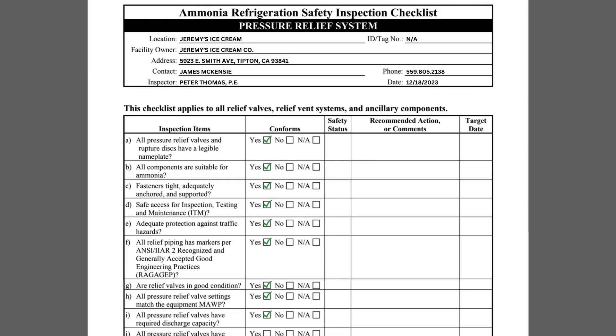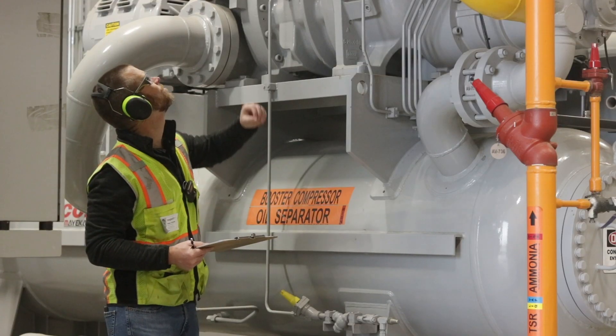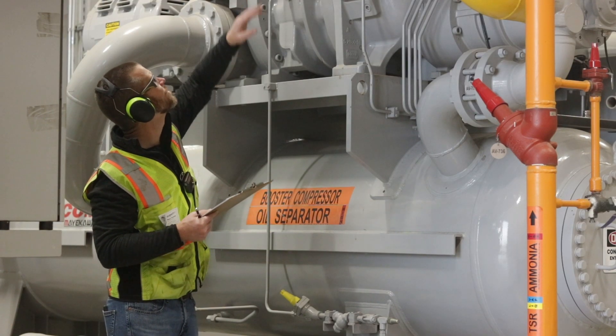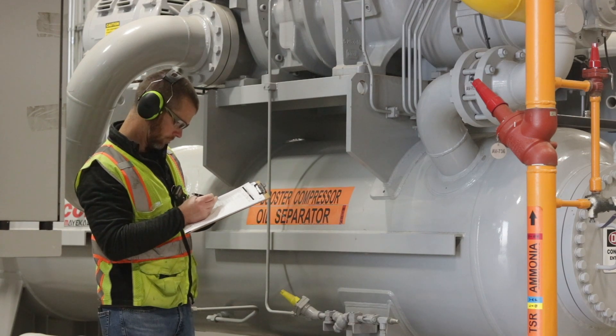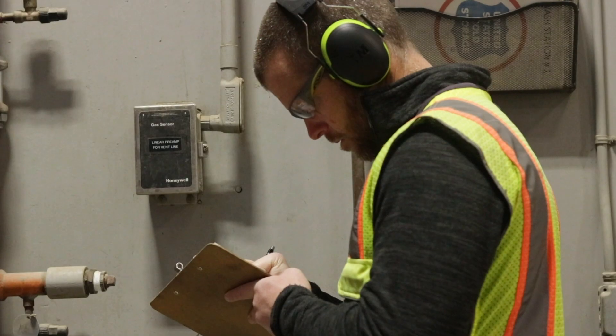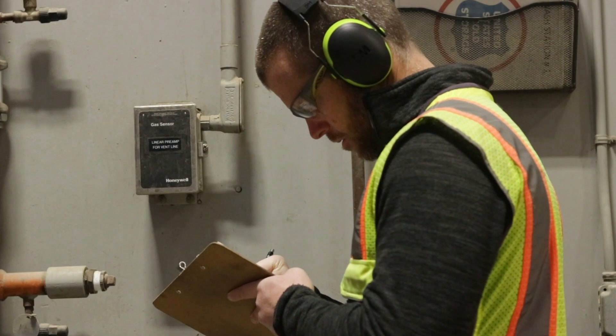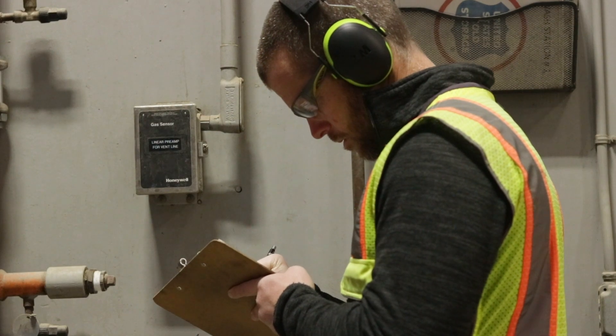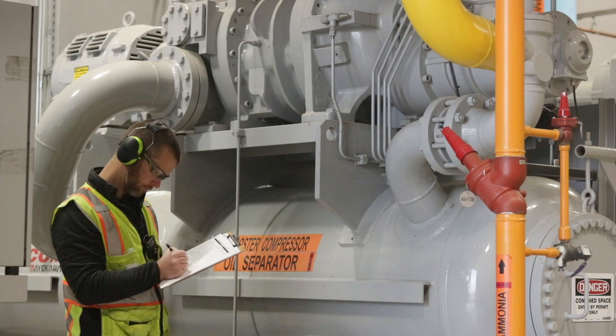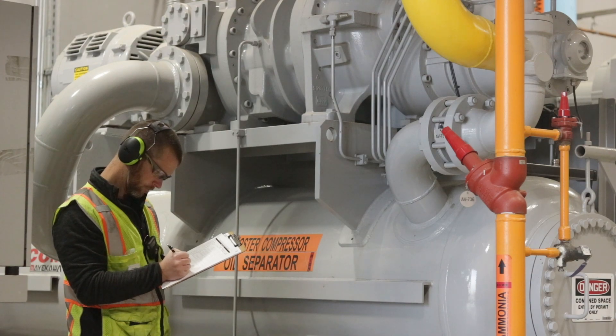Item I inquires if all the pressure relief valves have required discharge capacities. Explaining the rationale for assessing the required discharge capacity is outside the scope of this video, but at minimum, the inspector should verify that the relief system calculations are available and consistent with the relief system installation.